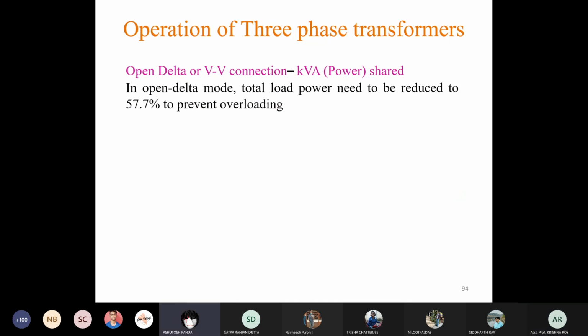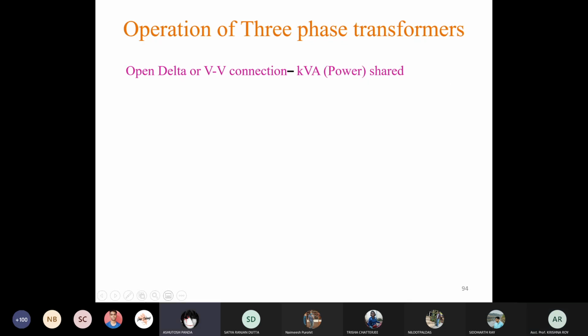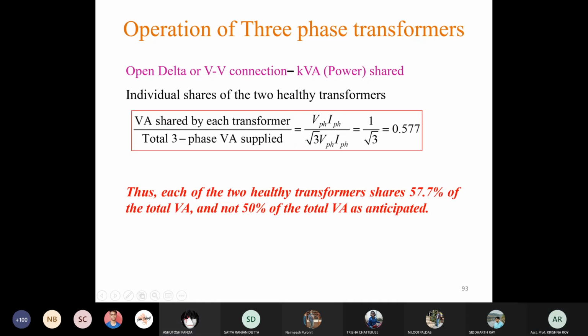In open delta mode, yes, 57.7% how? Sir, 57.7% in both. Yes. So then the total is exceeding 100%. No, not exceeding. See, each of the two healthy transformers shares 57.7% of total VA and not 50% of the total VA as anticipated.